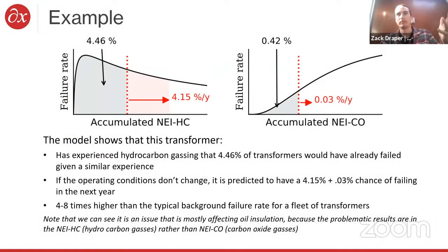An example of how we use this model in reliability-based DGA: we have this accumulated NEI, which is our observable in the gases. We have the model, we measure it for an individual transformer and compare it against the model, and it gives us statistics where the cumulative severity is 4.5%. That means 4.5% of transformers would have failed had they had a similar level of gassing up to the present day. Then we can project into the future and say, if it keeps gassing at the current rate, how much more risk am I adding to that transformer within the next year?